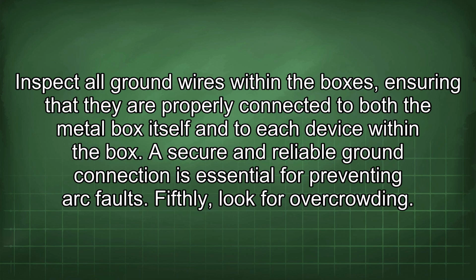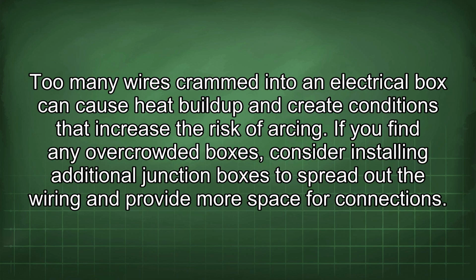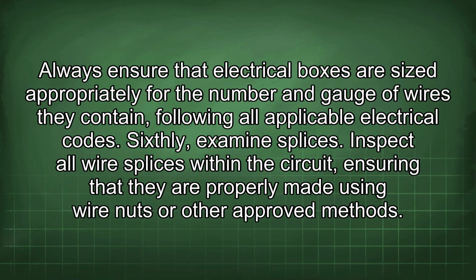Fifthly, look for overcrowding. Too many wires crammed into an electrical box can cause heat buildup and create conditions that increase the risk of arcing. If you find any overcrowded boxes, consider installing additional junction boxes to spread out the wiring and provide more space for connections. Always ensure that electrical boxes are sized appropriately for the number and gauge of wires they contain, following all applicable electrical codes.